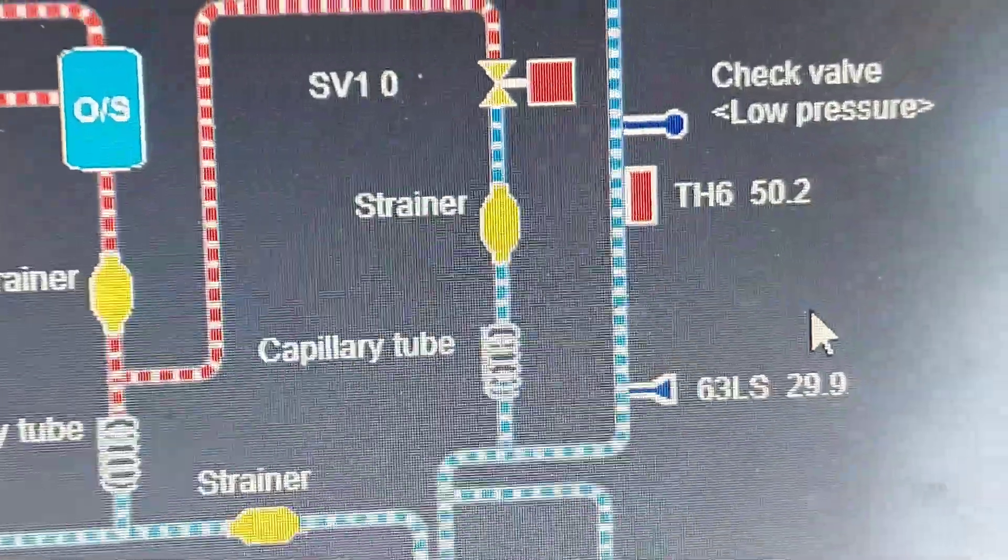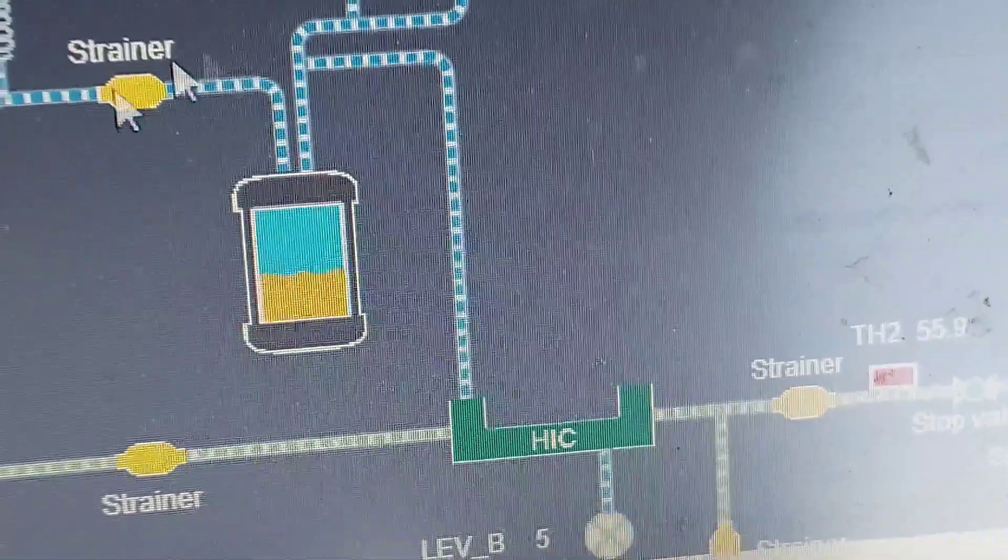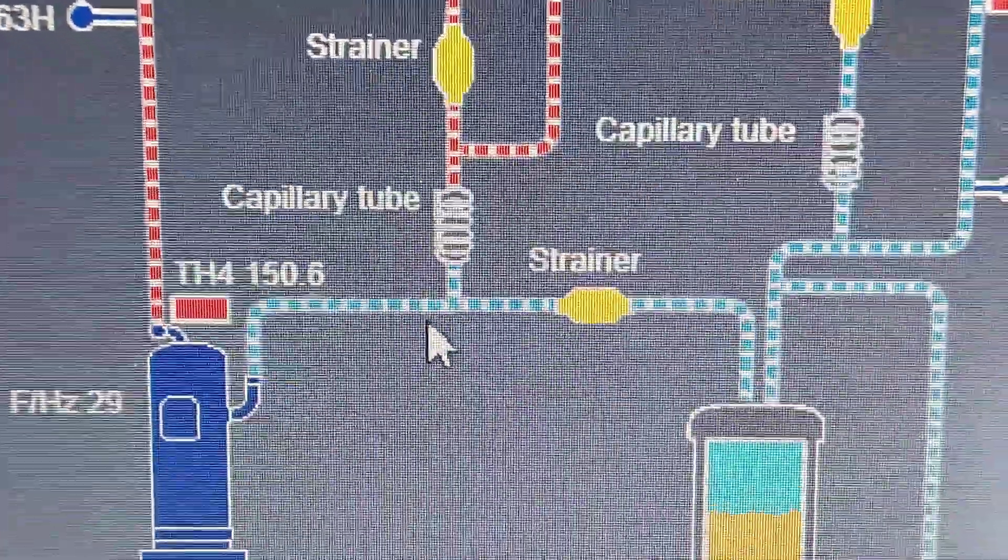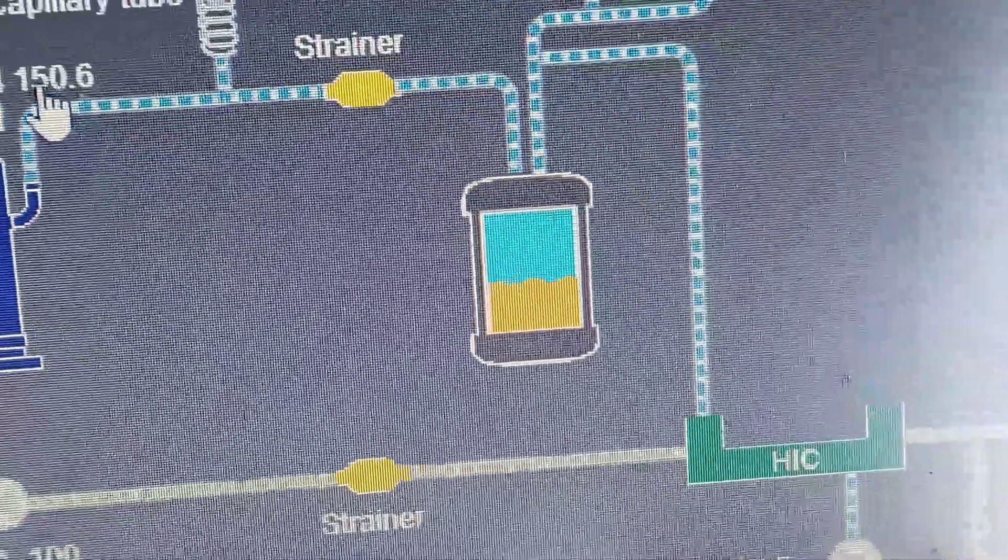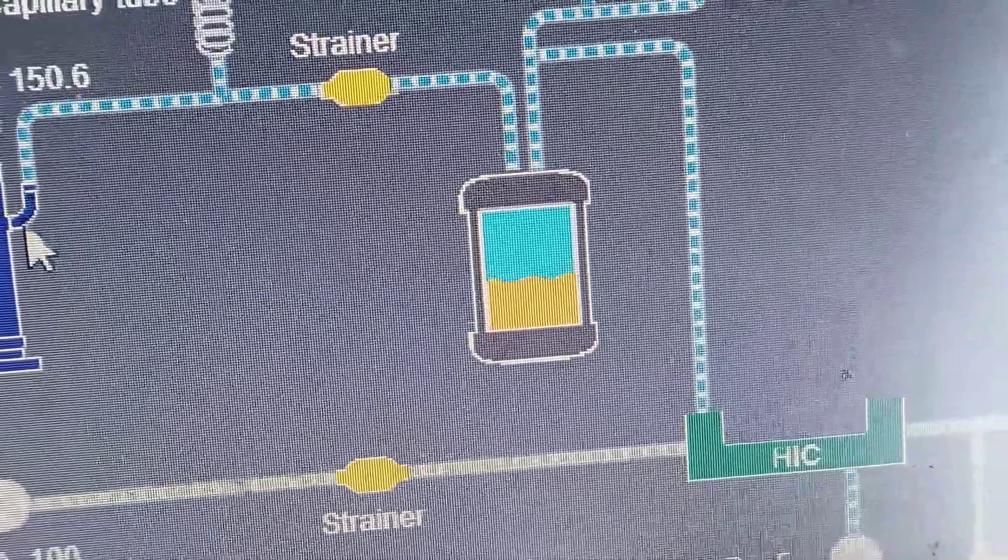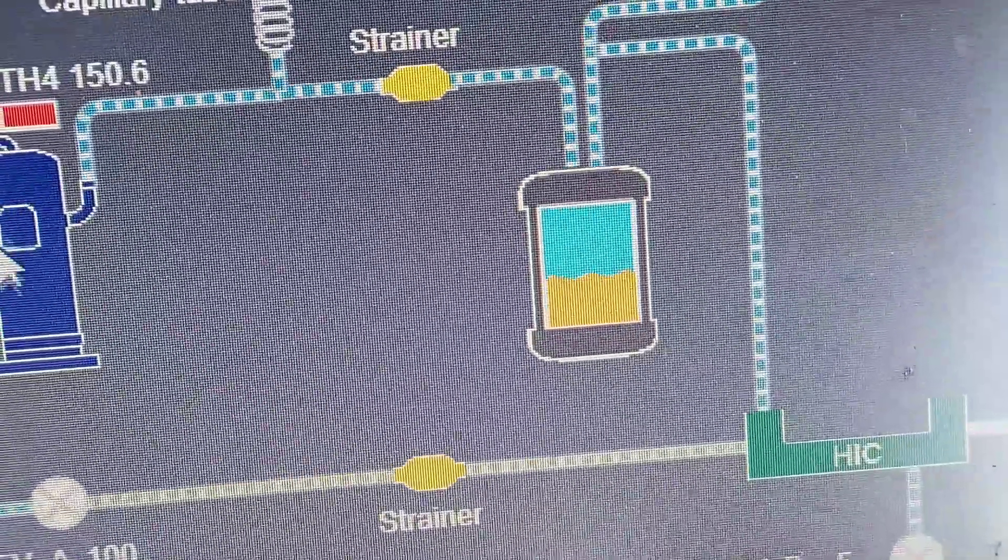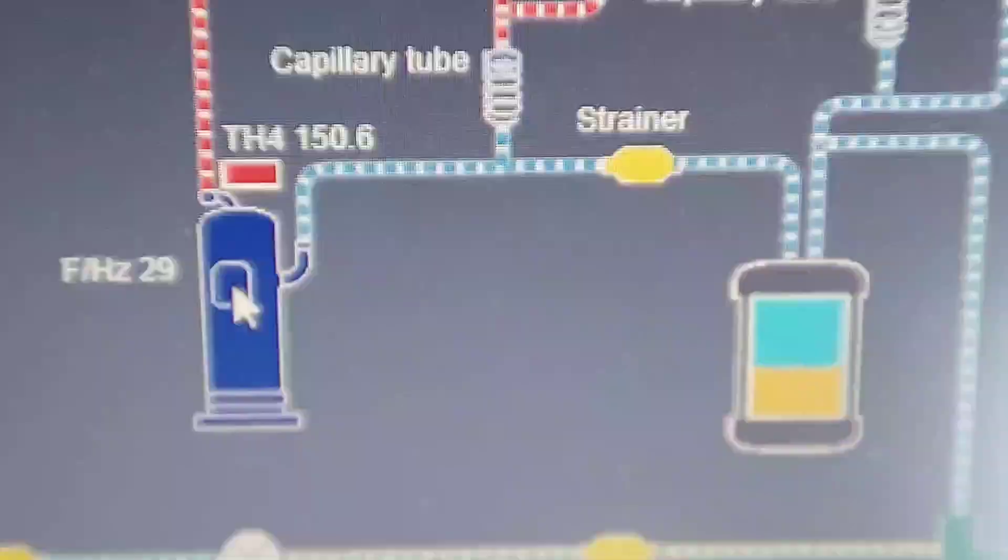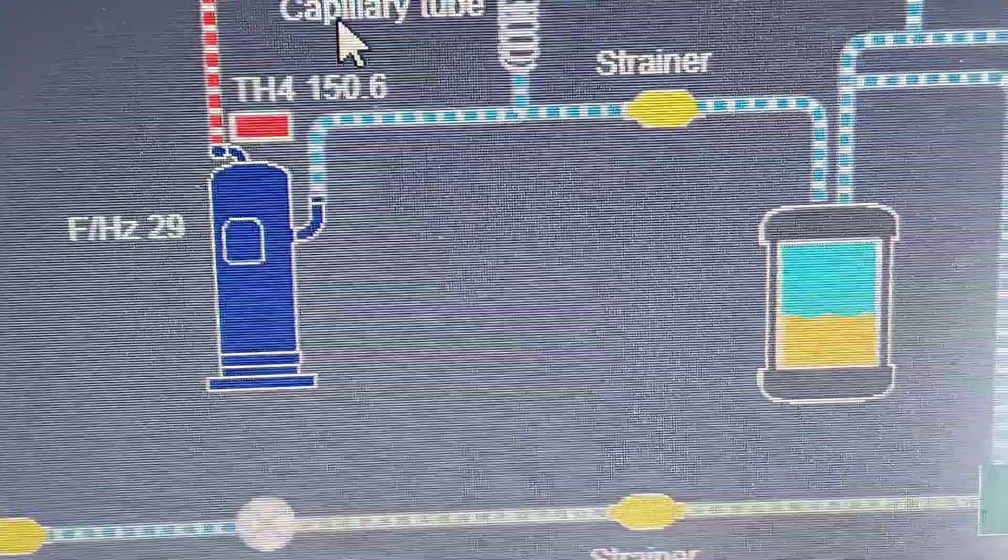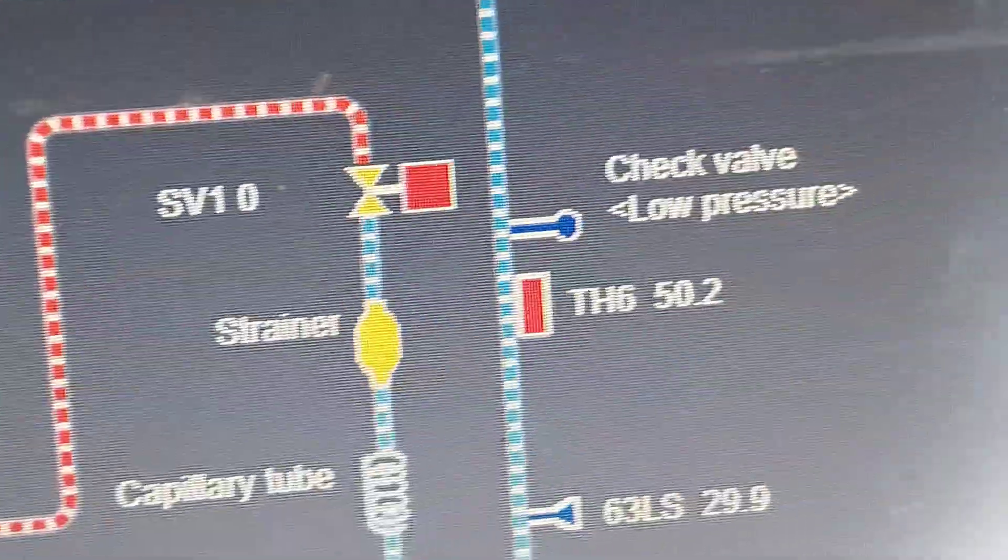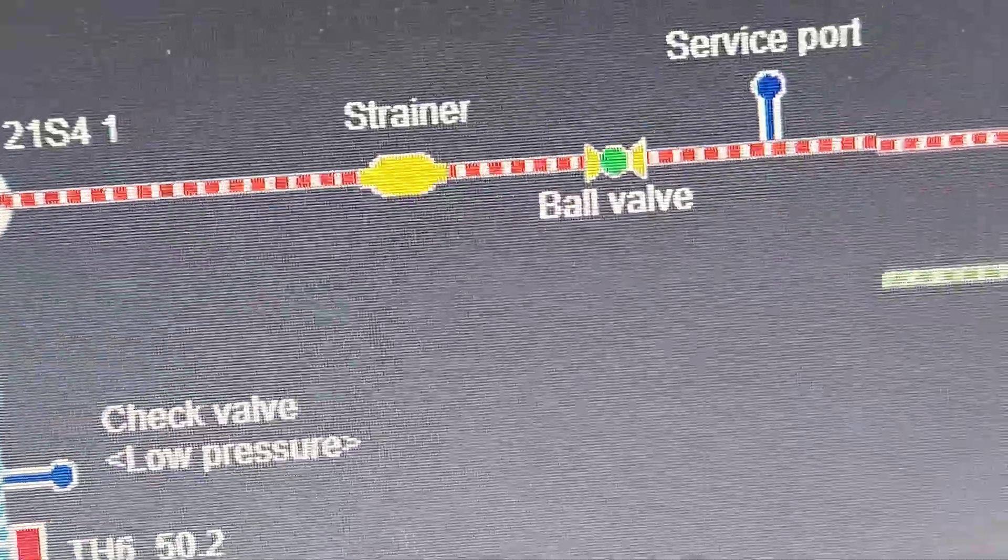OK. So yeah, I'm just going to head to the condenser right now and I'm going to add some refrigerant. And look, we're at 150 degrees here, that's all heat of work, actually the heat of compression. There's 150 there and we are only 68 over here. Oh, 68 on our indoor right here, see.